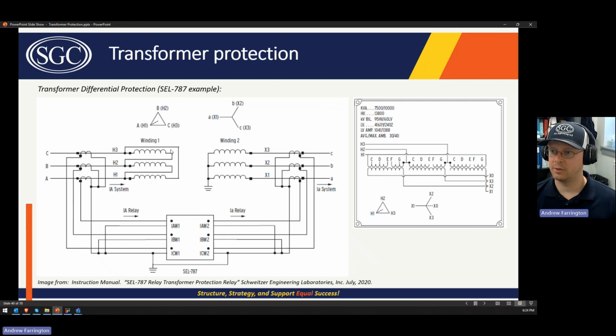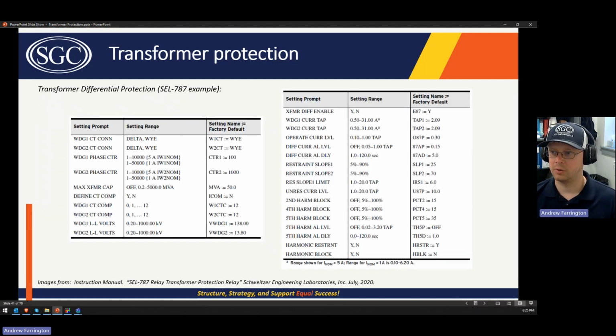If this were a YY transformer that was grounded on both sides, you may not need these compensation settings, because you don't have a phase shift with a YY transformer, and because both sides are Y windings with a grounded neutral, the only way that zero sequence current can flow through the transformer is if it flows through these CTs and then back out these CTs. So that's a case where you may be able to get away with setting that to no or N. But generally, you're going to have to account for some sort of compensation.